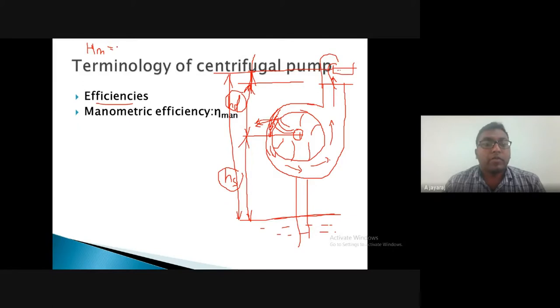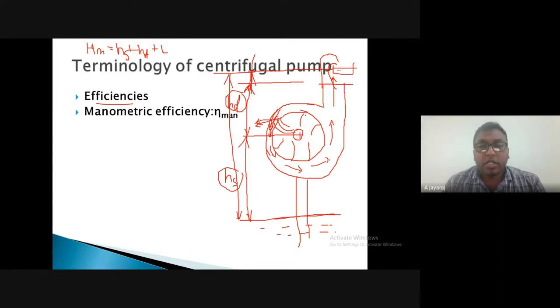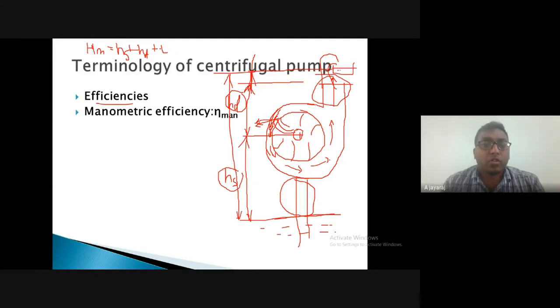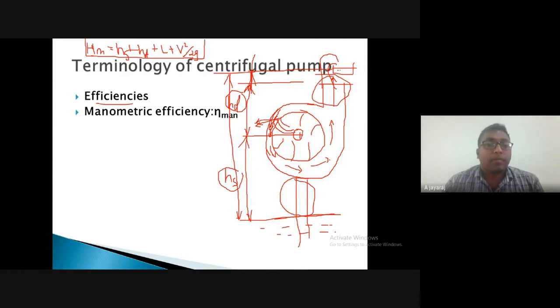The manometric head is the combination of all heads the pump must supply to complete its task — pumping water from the sump to the tank. It includes suction head, delivery head, frictional losses in suction and delivery pipes due to bends etc., and the velocity component of the water being supplied. This total head that the pump must supply to satisfy its requirement is called the manometric head.